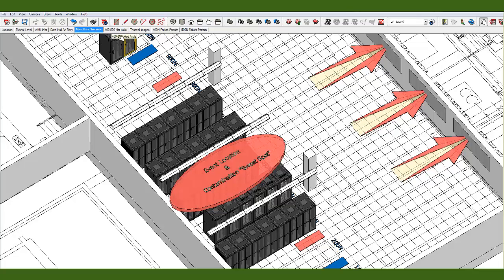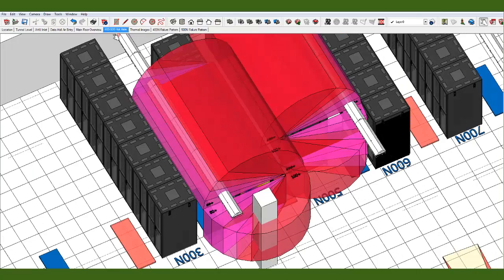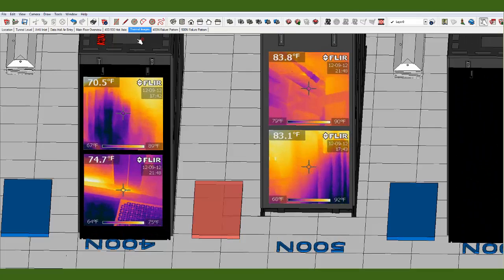And we were able to discuss also in the context of energy management. These are normal fluorescent lights, and they really threw off a heck of a lot of heat in there, along with the other problems they had with thermal management and other kinds of standard references for a data hall. They had a lot of problems that were discovered and illustrated in these heat images.